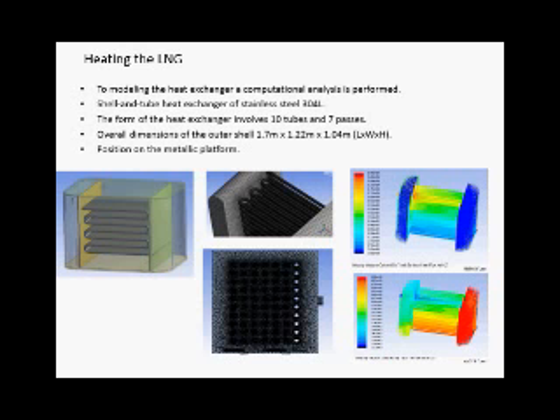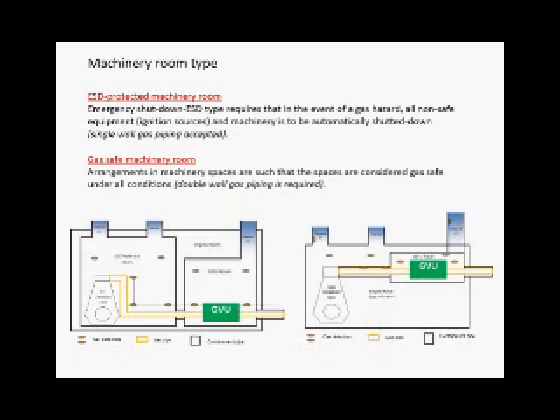Now we have the natural gas in gaseous form within the pipes, after the evaporator and the heater. But we need to feed this natural gas into the engine room. In this respect, two concepts were investigated: the protected machinery room, or emergency shutdown type protected machinery room, and the gas-safe machinery room.